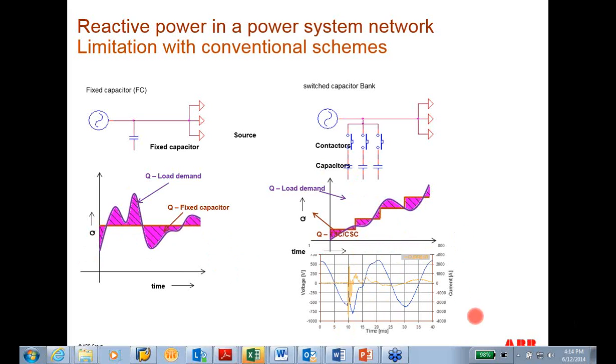When we go for the next technology, we call it stepless compensation. Stepless compensation is nothing but an IGBT-based inverter, a voltage source converter, which is mostly used to generate inductive power or capacitive power or unbalanced compensation, as well as harmonics compensation to some extent when necessary.